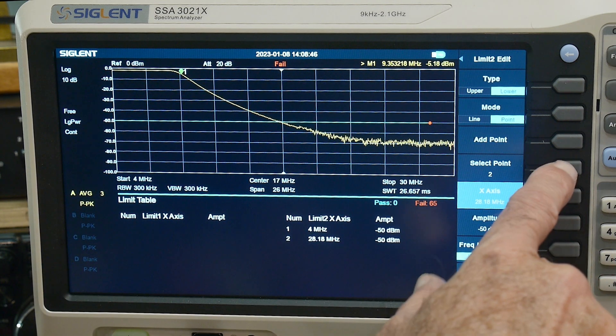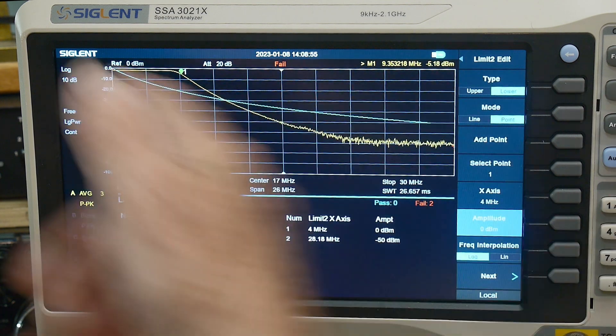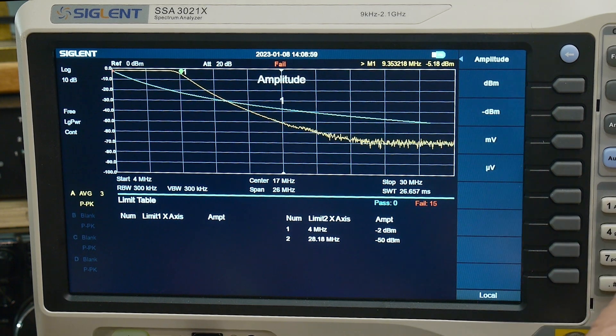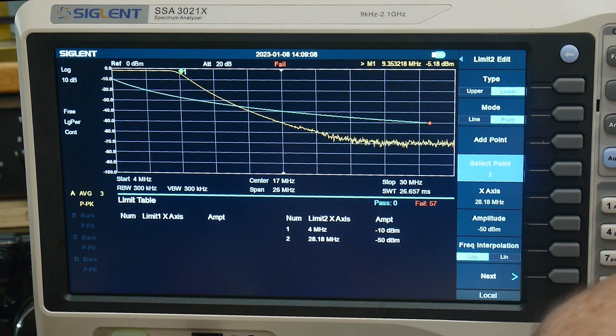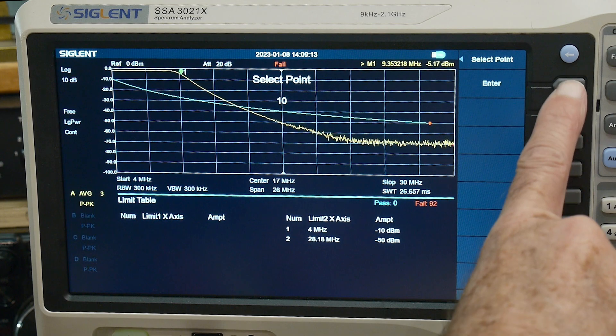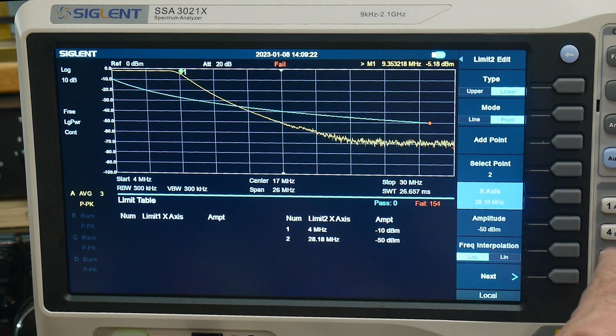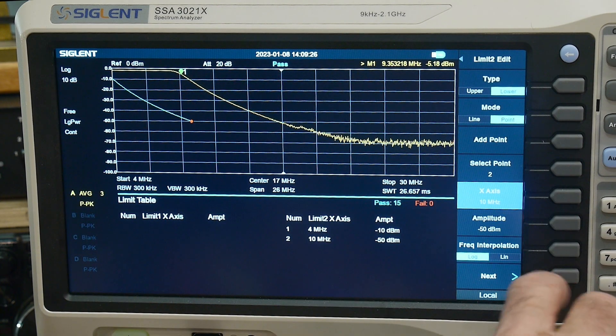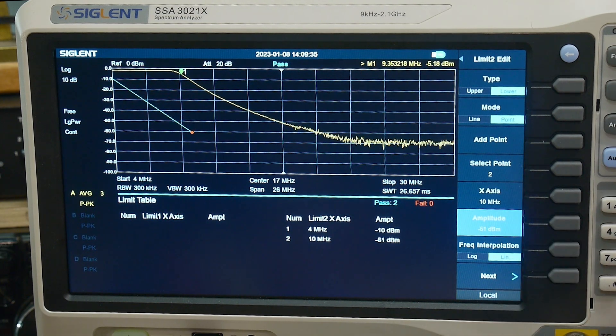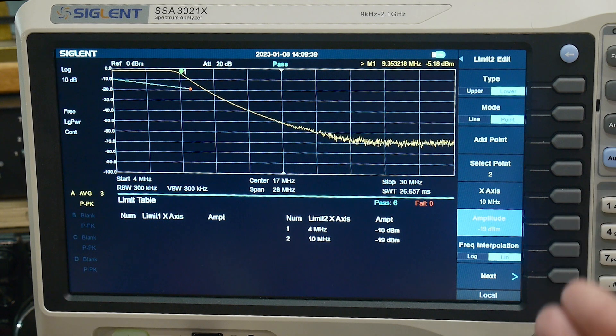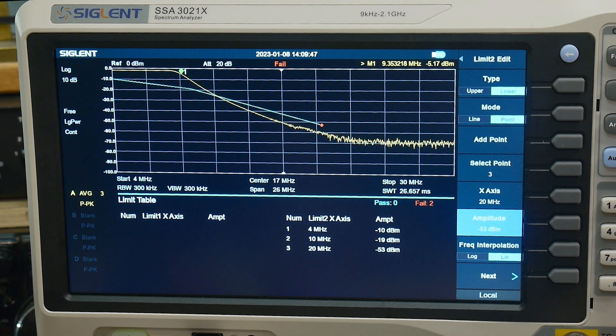With the buzzer off, we now have a line. We can set the starting point — select point one and change where it is. Maybe we'll set it at minus 10 dBm. Then we set the second point: select point two, put it at 10 MHz on the X-axis, choose linear interpolation, and set the amplitude. Now we can draw a line anywhere we want — add another point at 20 MHz and change the amplitude there too.